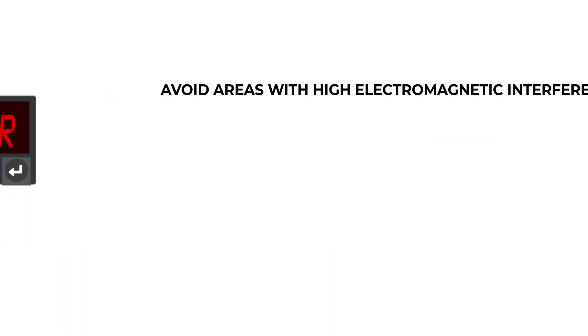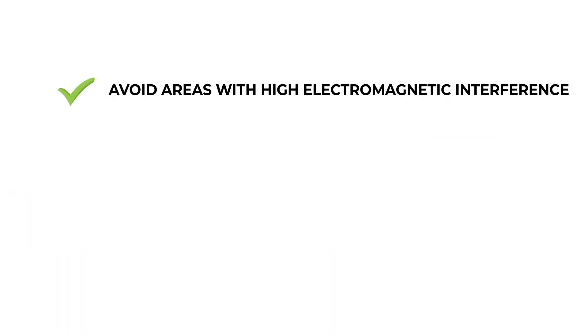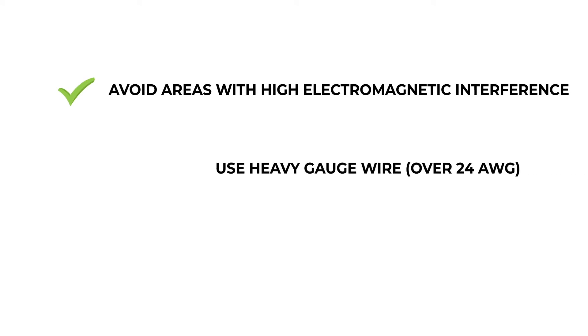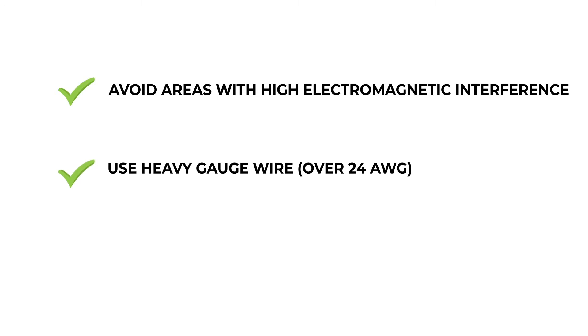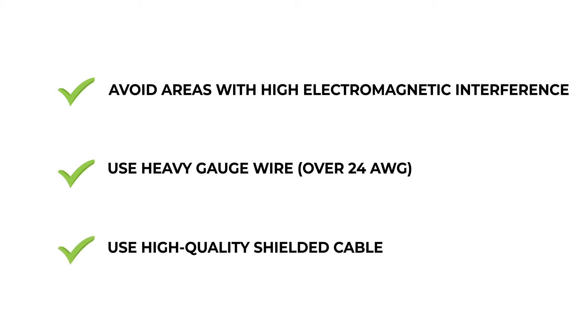Ideally, you should avoid areas where there's a lot of electromagnetic interference. But as we all know, sometimes that's just not possible. Using a heavier gauge wire will help reduce the amount of noise. We recommend a minimum of 24 gauge. Shielded cable also helps to a degree, but if the distance from the sensor to the indicator is too far, no amount of shielding will ensure that your signal is strong enough to be read accurately.